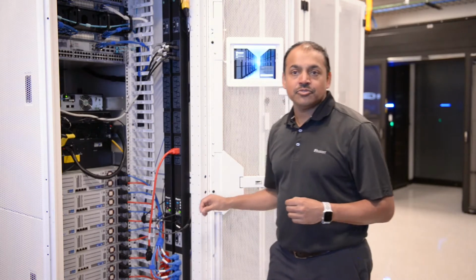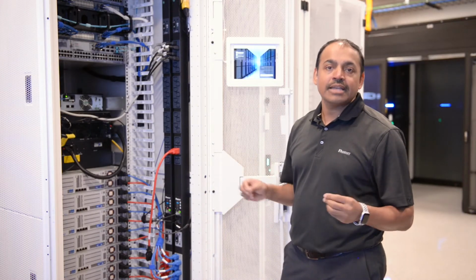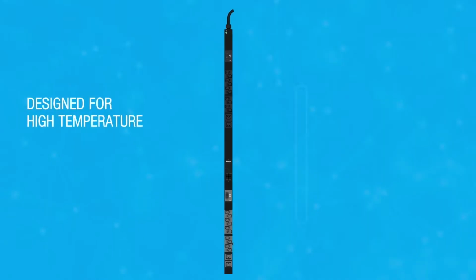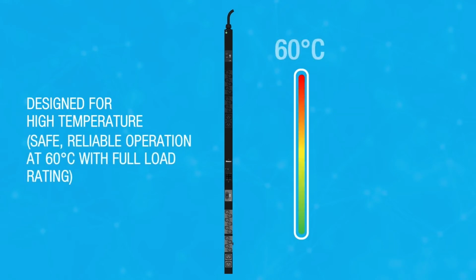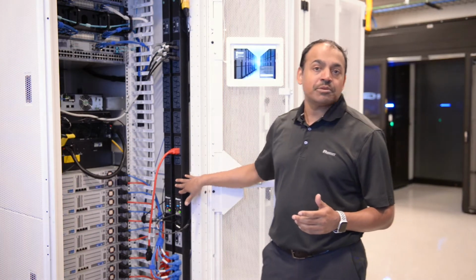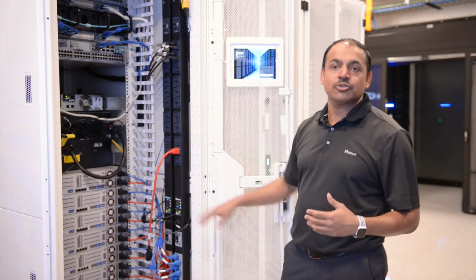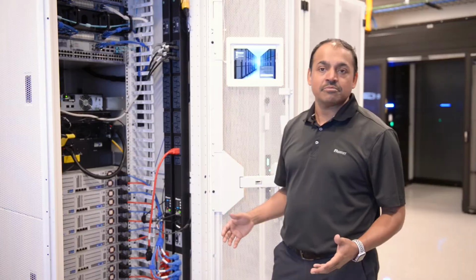All Gen 5 PDUs are designed with premium high temperature components, enabling them to reach an operating temperature of 60 degrees C, or 140 degrees Fahrenheit. This is because PDUs typically reside in the hot aisle, and we wanted to make sure the product was built to survive that environment.